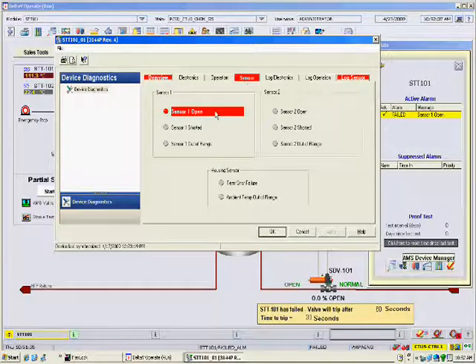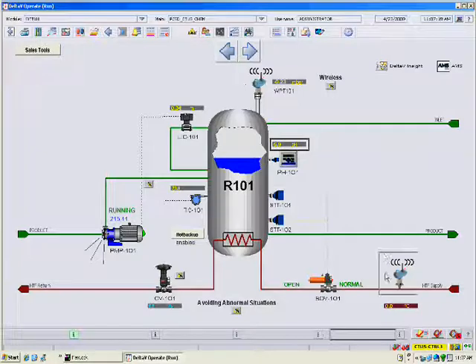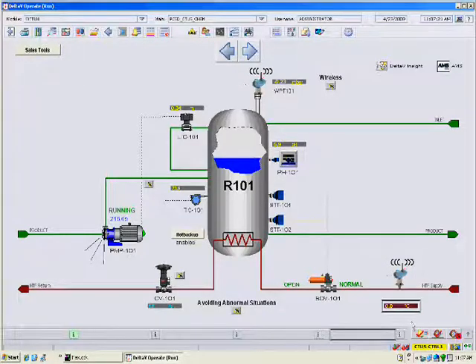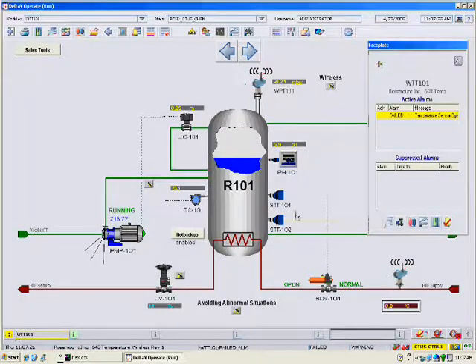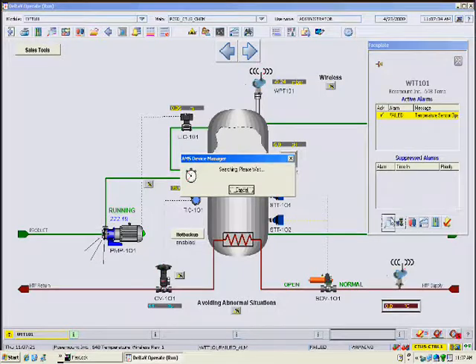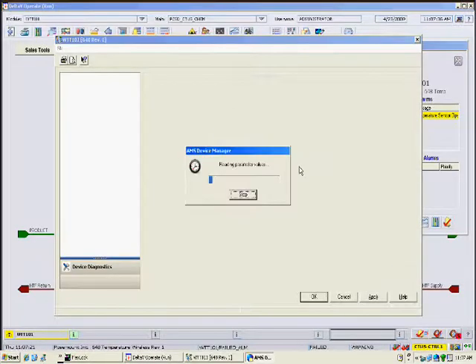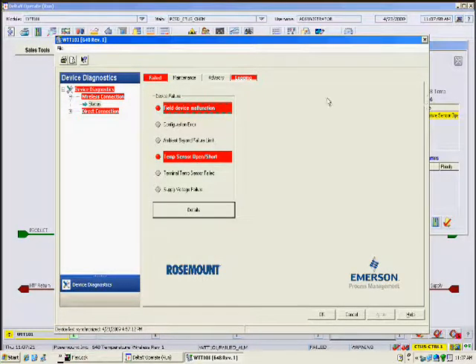The operator follows the red tabs to see the details of the failure. In this case, it is a sensor failure. In this last example, let's look at a wireless HART temperature transmitter. The system is continuously monitoring the health of all wireless HART devices. The device alert appears and the operator clicks on the alarm banner, which opens the device faceplate. In this case, the faceplate shows it is a serious device failure. The operator opens detailed diagnostics at a click of a button. The detailed diagnostics is displayed, rendered by the system as intended by the device manufacturer based on the EDDL file.